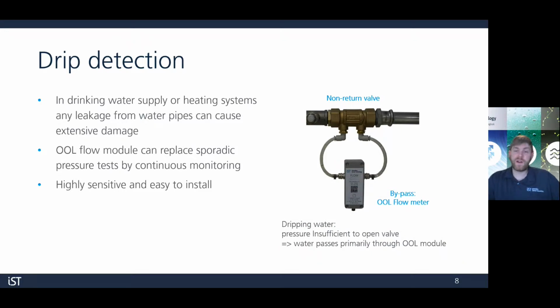With all our faucets turned off, we'll still have a very small flow of water going through the pipe and the OOL due to the dripping faucet. Since the OOL has high sensitivity in the low flow range, we'll be able to detect this leak. This leak detection method can potentially replace more extensive pressure testing.